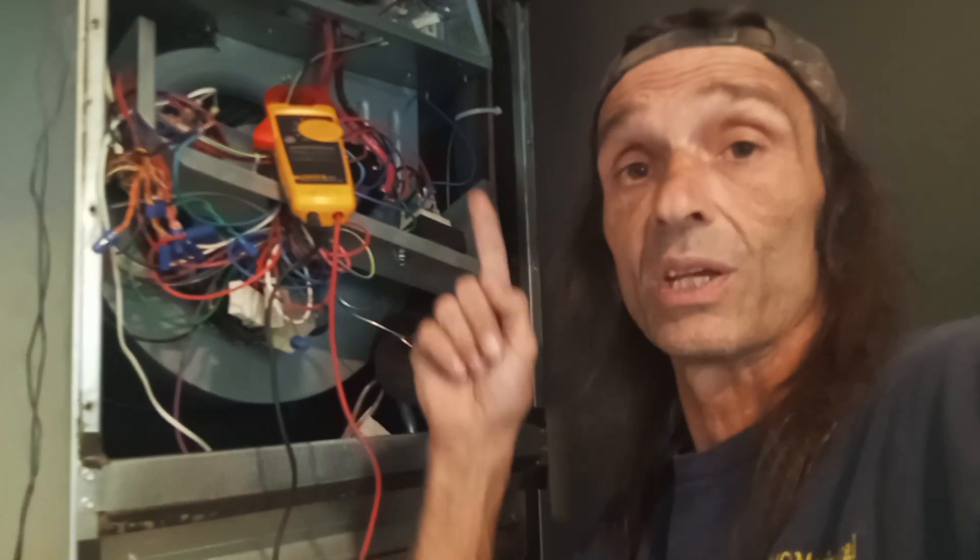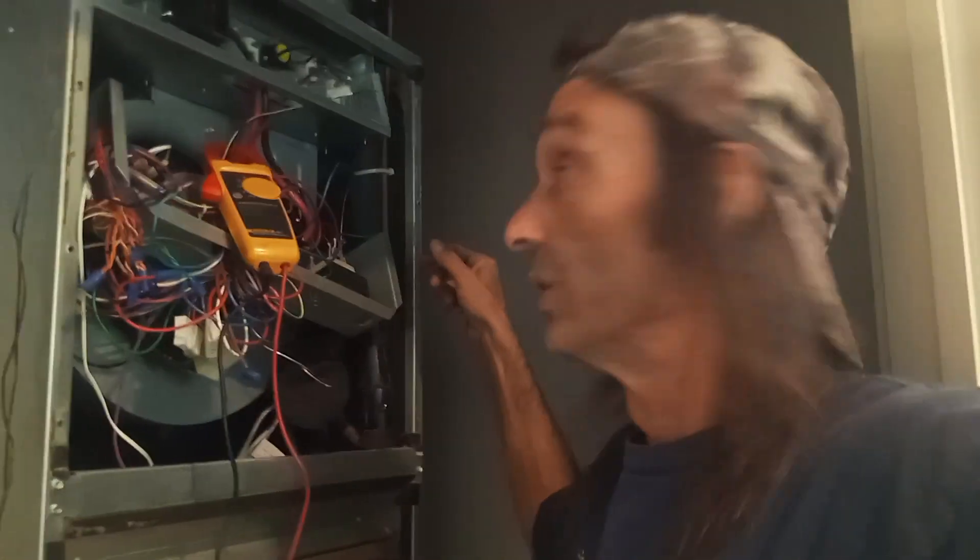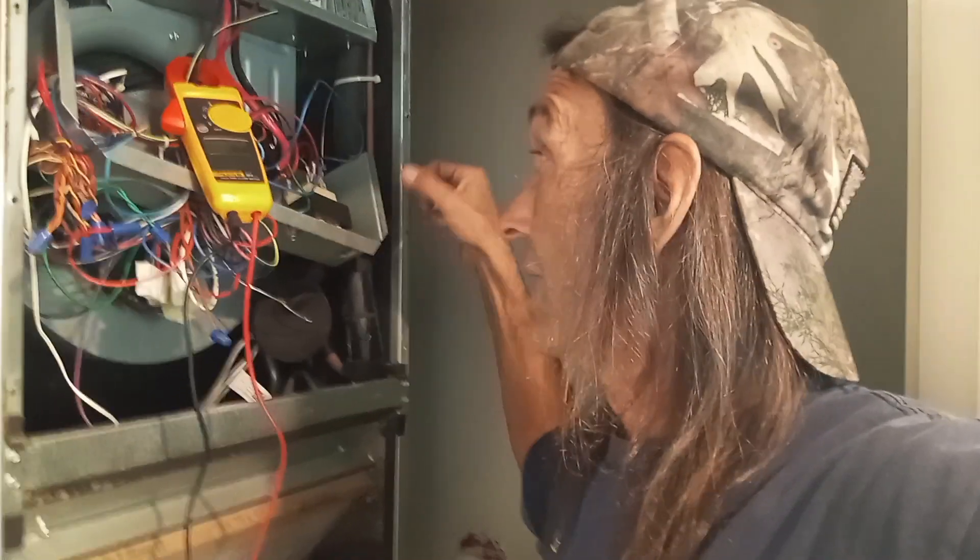But literally watch this blower motor try to start with the disconnect out. I noticed a couple sparks when we were moving the case around. I don't want to do it right now because this unit is hot — everything in here is hot. If I touch the wrong stuff I'm getting shocked. Now we've got to figure out what's doing it, so we're going to go to the roof and look for some wires or something shorted out.